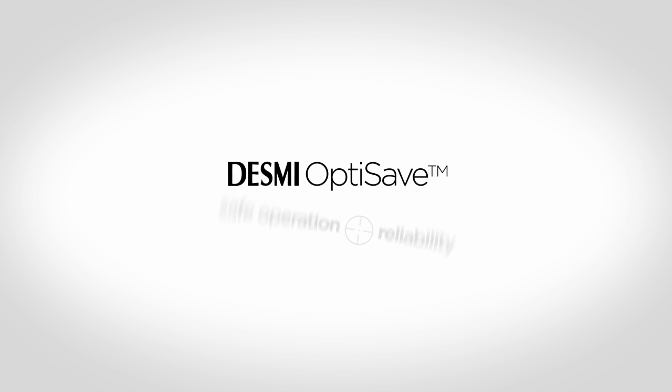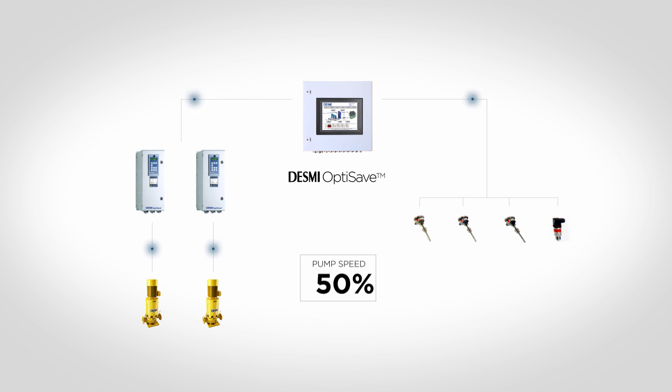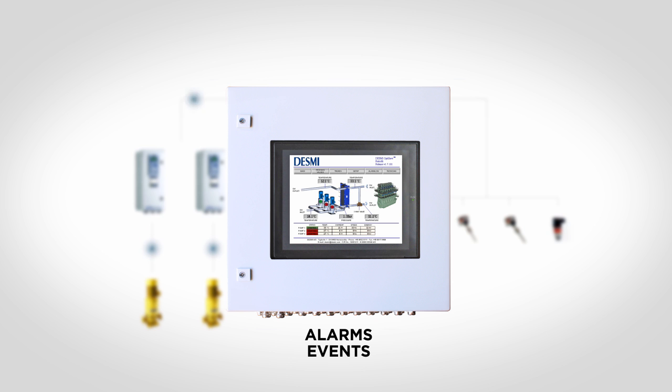When DESMI designed the OptiSave system, one of the main focus areas was safe operation and reliability according to class requirements. This has been done by incorporating a number of fail-safe modes. For example, if a wire for a sensor breaks or if the master control panel is powered off, the speed of the pumps increases automatically to 100% speed to ensure sufficient cooling. The intelligence of the system ensures maximum savings and safe, reliable operation. Furthermore, all alarms and events will be logged and can be transferred to the alarm system on the vessel.